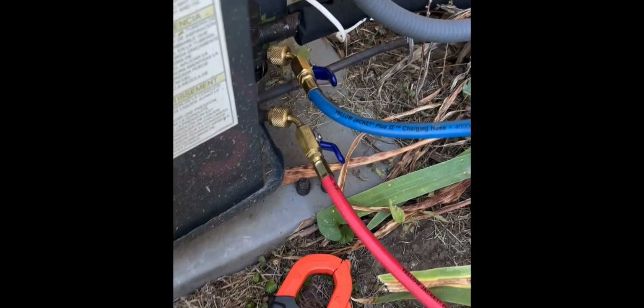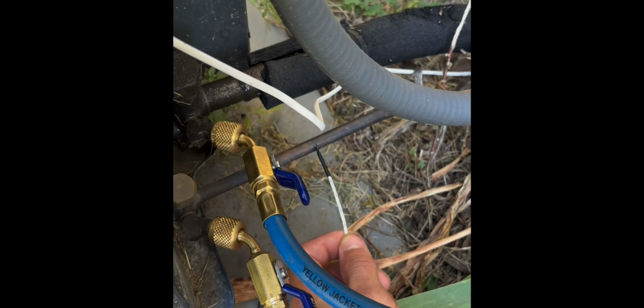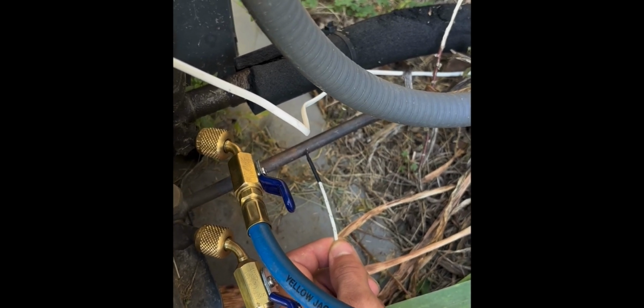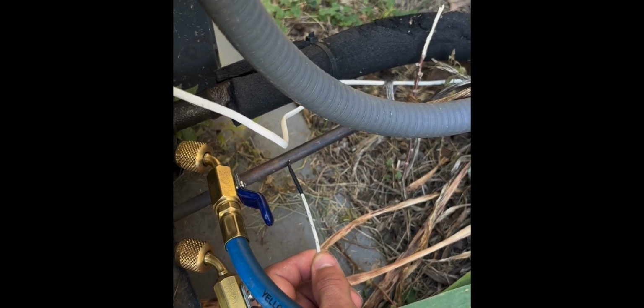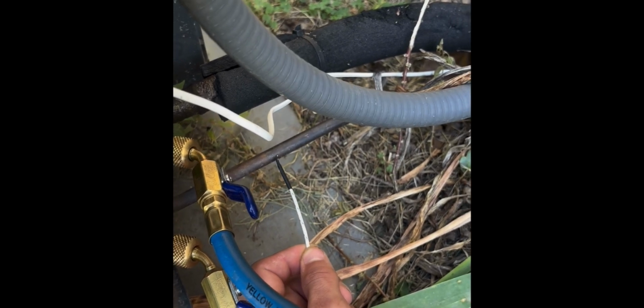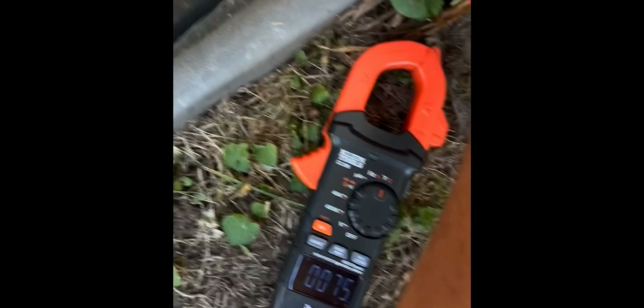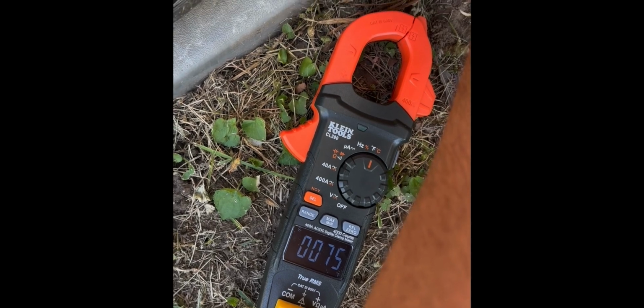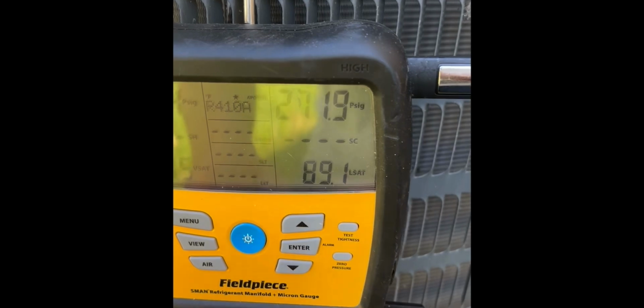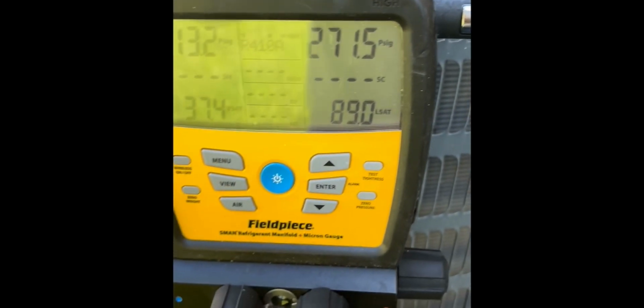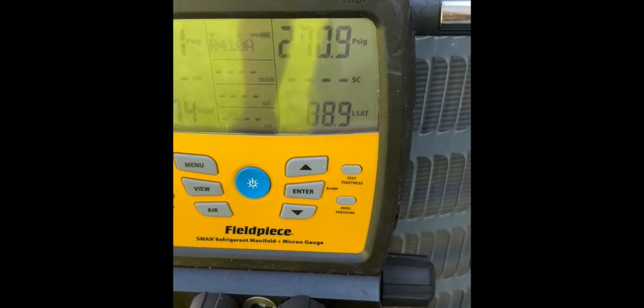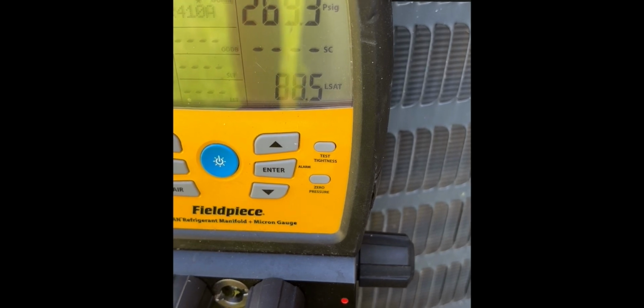Now to find subcooling, you just go ahead and set your probe on there. If you're getting a reading for a longer amount of time, you want to put some tape on it, but for right now we can just hold it on there and that'll work. And right now we're at 75, so we want to remember that. When we come over here, we take our saturated temp right there, and we want to take 89 minus 75, which gives us about 14 degrees subcooling. So we are a little overcharged, but not too bad.